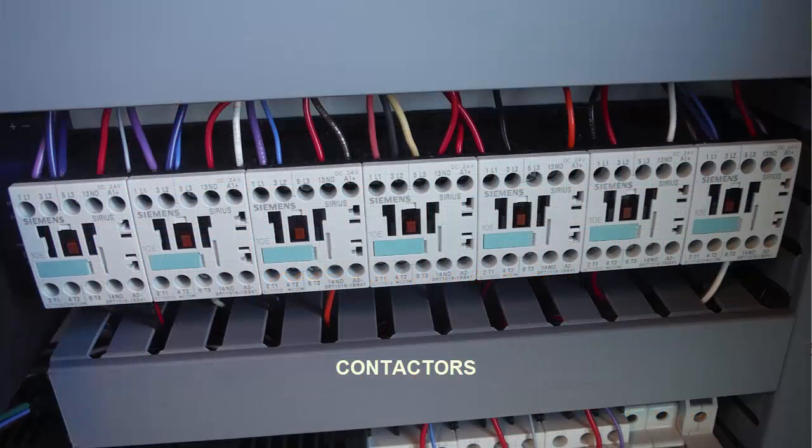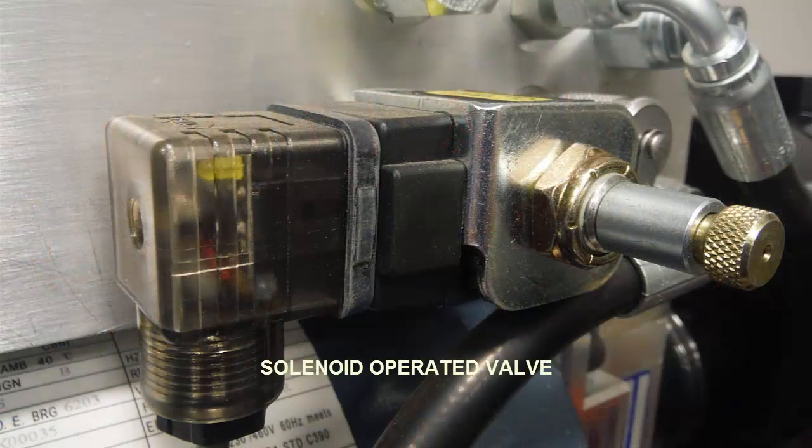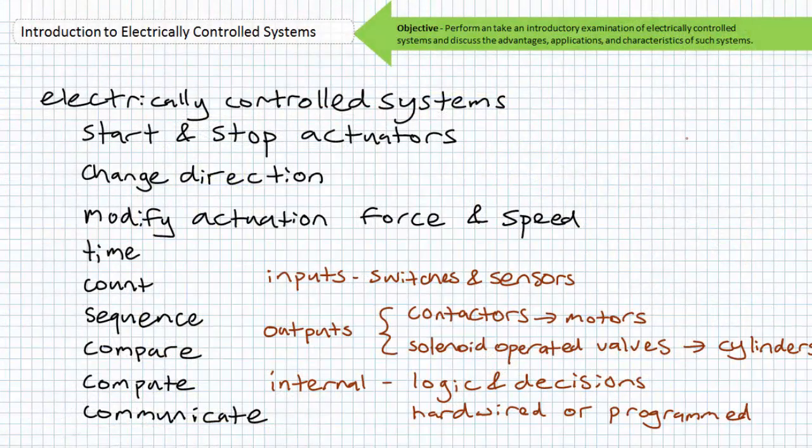A contactor starts or stops a motor. The solenoid operated valve extends or retracts a hydraulic cylinder. If the motor is disconnected from the contactor, or the system doesn't close the contactor, the motor won't start. If the cylinder doesn't have fluid supply, or the solenoid operated valve doesn't shift, the cylinder won't extend or retract.